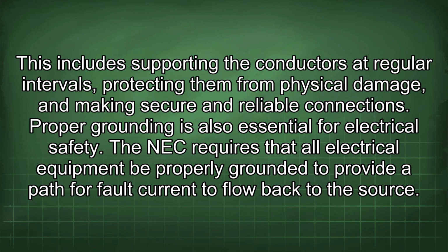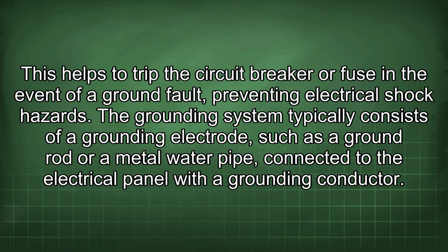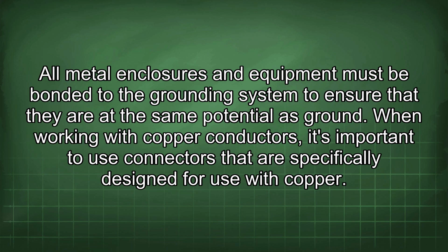The NEC requires that all electrical equipment be properly grounded to provide a path for fault current to flow back to the source. This helps to trip the circuit breaker or fuse in the event of a ground fault, preventing electrical shock hazards. The grounding system typically consists of a grounding electrode, such as a ground rod or a metal water pipe, connected to the electrical panel with a grounding conductor. All metal enclosures and equipment must be bonded to the grounding system to ensure that they are at the same potential as ground.